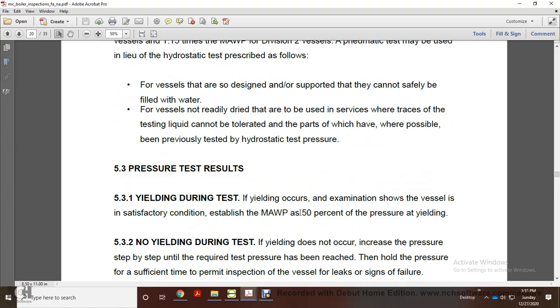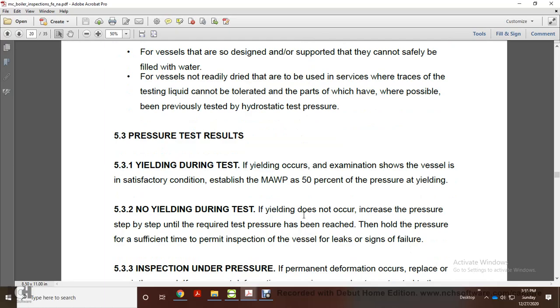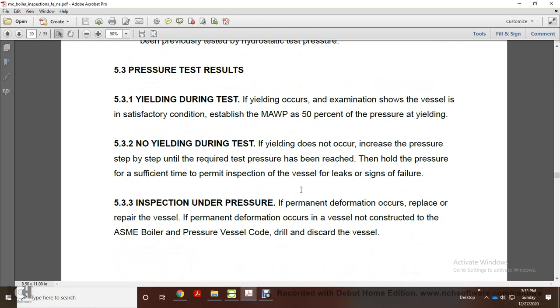Examination establishes maximum operating pressure at 50% of the pressure at yielding. No yielding during the testing. If yielding does not occur, increase the pressure step by step until the required test pressure has been reached. Hold the pressure for sufficient time to permit inspection of the vessel for leaks and signs of failure.